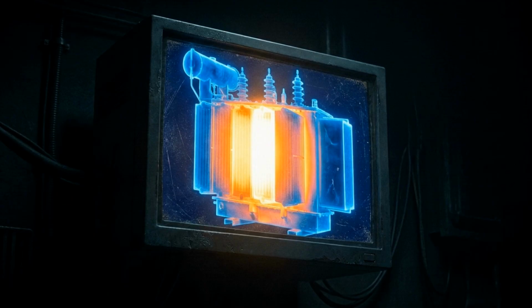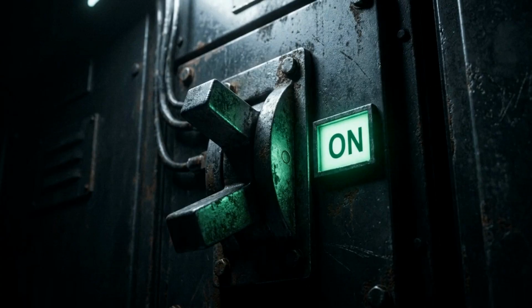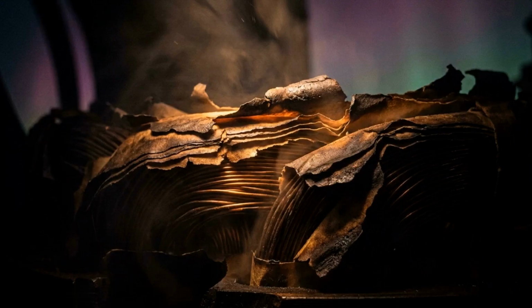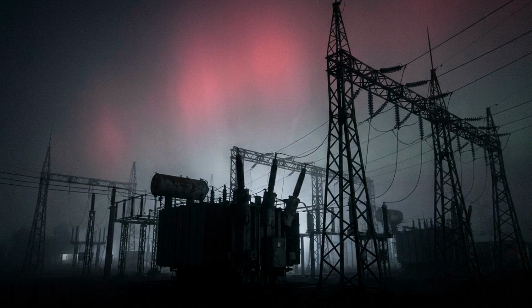The insidious part of this process is that it rarely trips the safety breakers. Instead, the heat slowly bakes the paper insulation inside the coils, invisibly degrading the internal components. Our transformers absorbed the invisible damage of the May 2024 storm, significantly accelerating their path to mechanical failure.